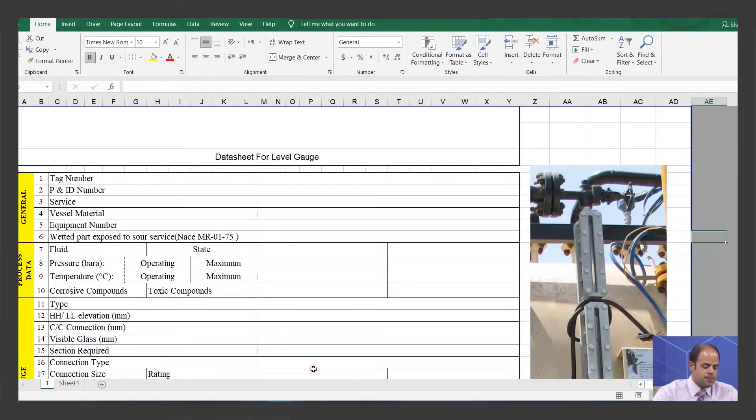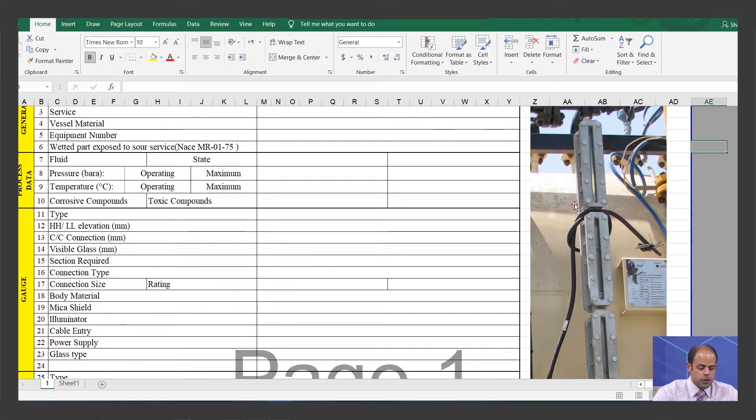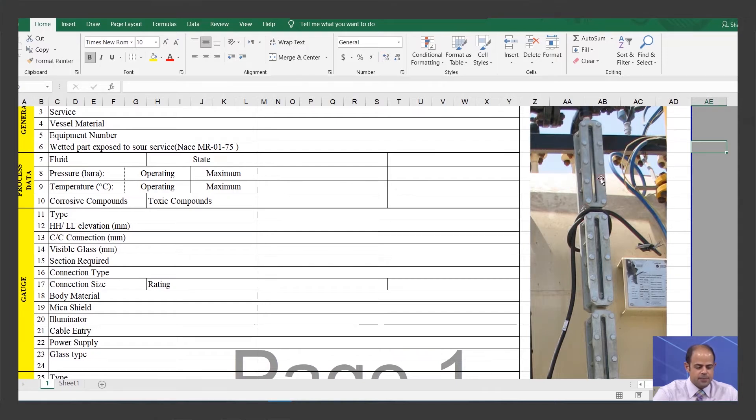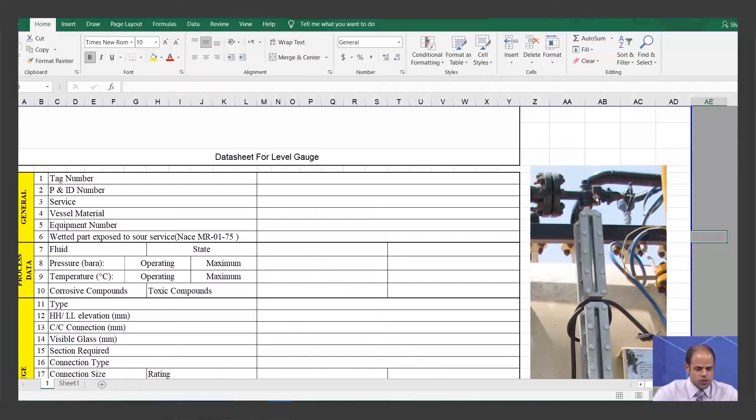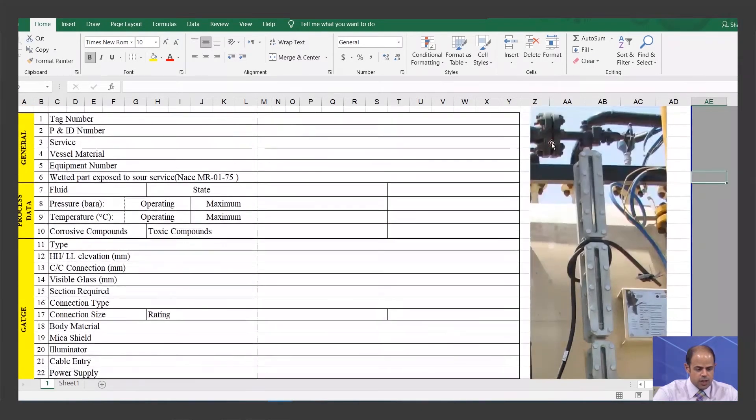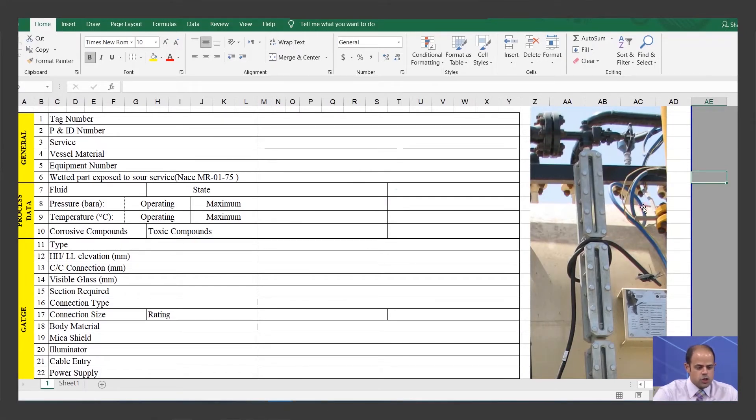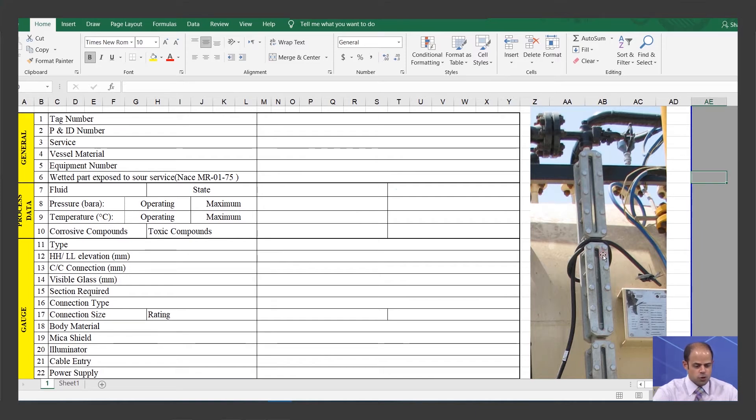So come to the level gauge data sheet. First, I deliberately brought a picture for you and put it here, because first of all you can see the different sections of the level gauge. It's a three-section sight glass. You can see the cock valves or gauge valves of these items too. And you can see these flanges related for connection to the piping valves as well. When you want to fill up this data sheet, you can take a short glimpse on this picture and review the previous items that I told you on the whiteboard.